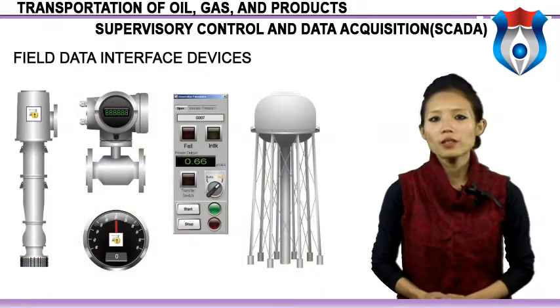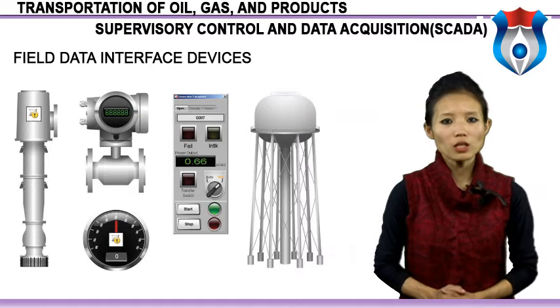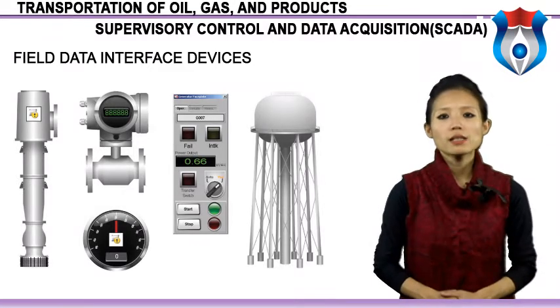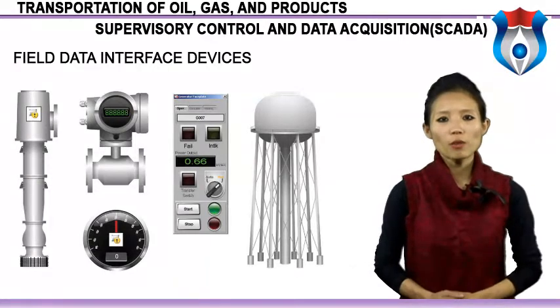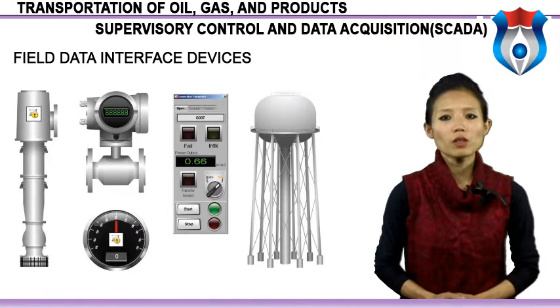Field data interface devices form the eyes and ears of a SCADA system. Devices such as reservoir level meters, water flow meters, valve position transmitters, temperature transmitters, power consumption meters and pressure meters all provide information about how well a system is performing. Before any automation or remote monitoring can be achieved, information passed to and from field data interface devices must be converted to a form compatible with the SCADA system language. RTUs — remote telemetry units — provide this interface. This provides an oil and gas SCADA solution without having to buy new hardware or control systems.